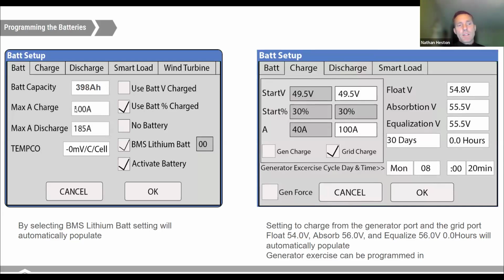For a single stack of 6.6s, this can be 195 amps DC. The max the Sol-Ark will do, I think, is 270 amps. And then on the discharge side, you would set it at the maximum. A Sol-Ark 15K will pull about 250 amps of discharge out of the batteries at 50 volts. You can go ahead and set that at the maximum value, which is 273. The BMS will automatically select use battery percentage. That's what most customers prefer. So if you do have a communicating battery, it'll set that. If you don't have a communicating battery, you can choose to use voltage.